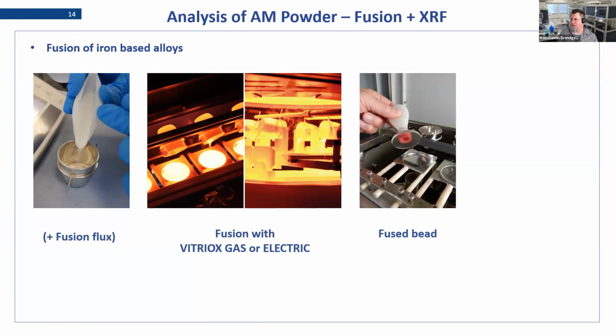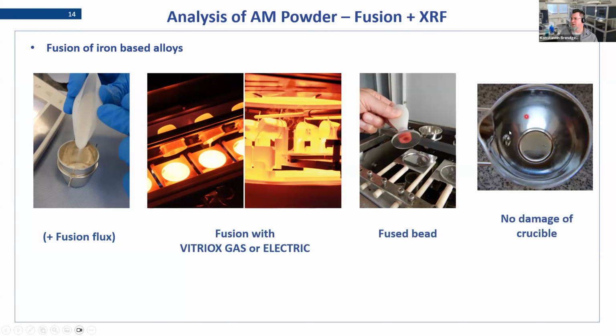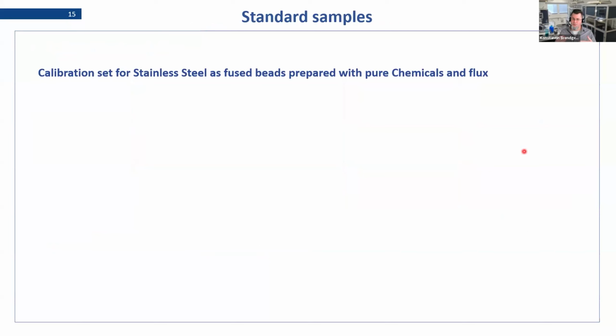The whole idea here is to get a good fused bead, and most importantly, to prevent any damage to the crucible. The problem with metallic powders, you're probably aware of this. There's also, I think, another episode of this series where we talk about it. Platinum is dangerous to work with metallic samples in general, so you have to stick to these procedures to get your fused beads without damaging the equipment and your platinum ware in the end. You want to use it for as many fusions as possible, so you want to be careful.